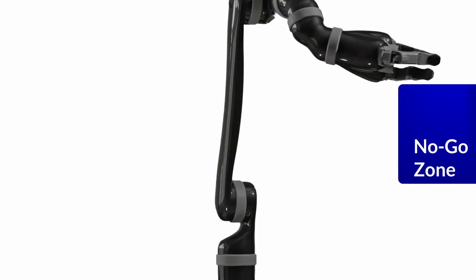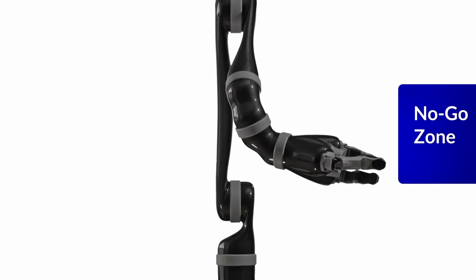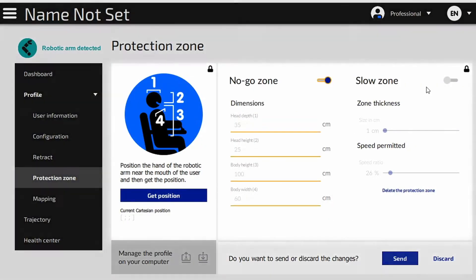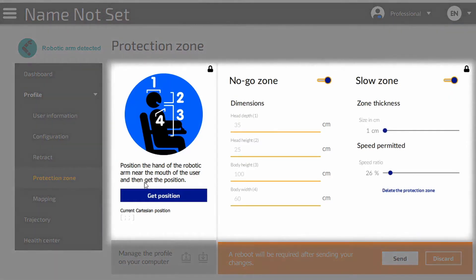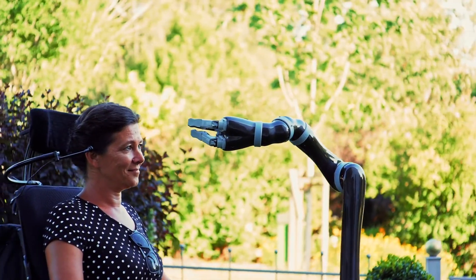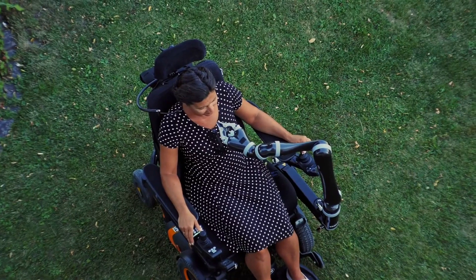For safety, Jaco has a protective feature called the no-go zone. This is a programmable zone around the user's face and upper body area, which can be adjusted to the head and body size of the user. Jaco first slows down its speed to finally stop in front of the face, if the user continues to move the joystick in that direction.